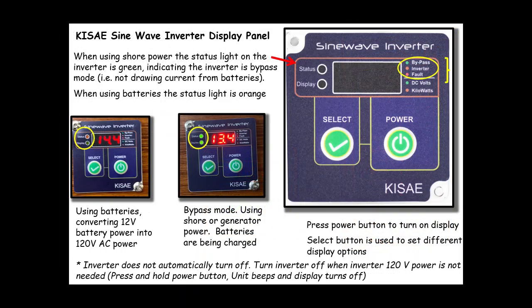Just a quick review: if we look at the inverter display panel, we have two status types. If the LED is green, that means the inverter is being bypassed and the charger is being used, and we're on shore power. If the status light is orange, that means we're using the inverter as an inverter, so we're draining power from our batteries to generate 120 volt AC power.